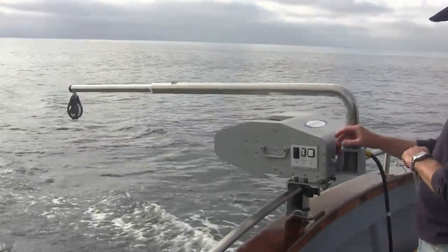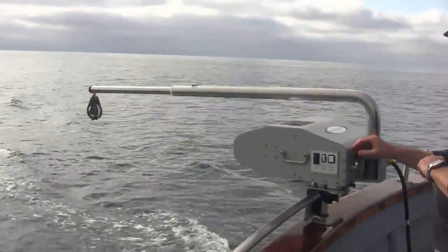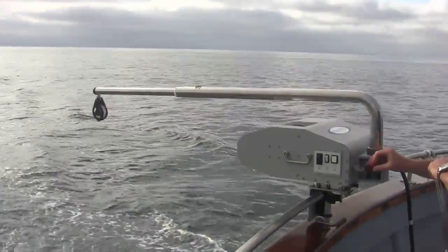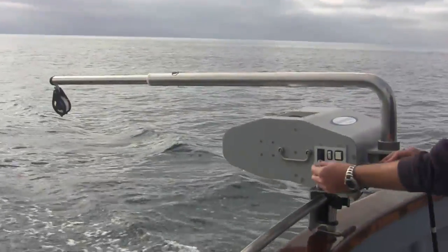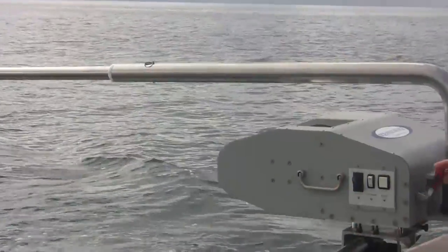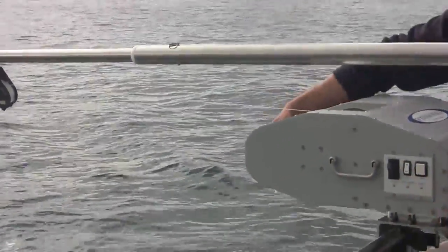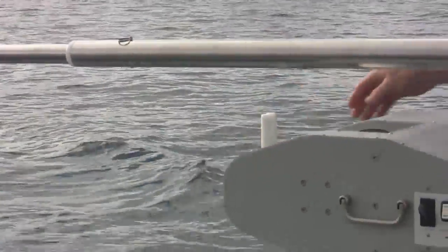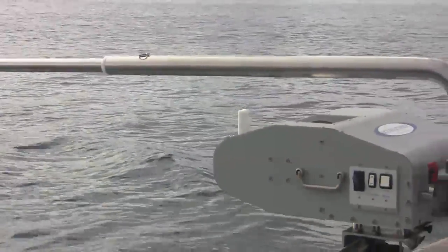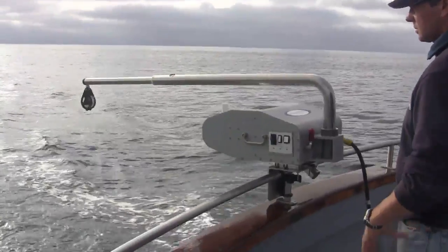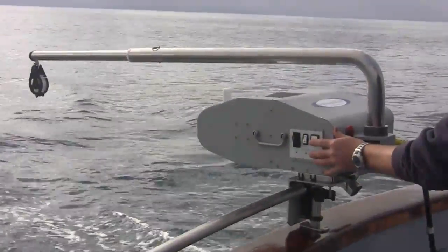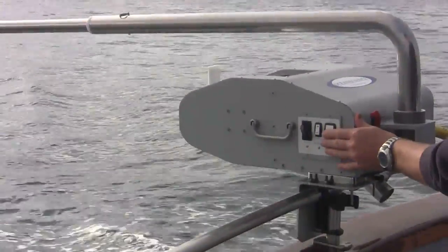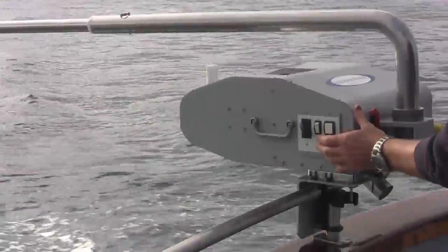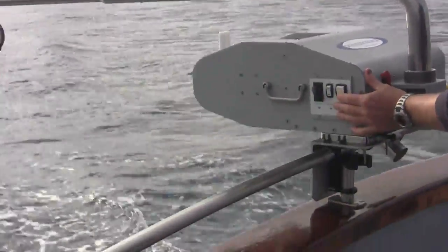So when the designated time has elapsed, the brake is applied, and then the clutch moves to the full position to lock the spool. Then you can let go of the brake, turn the level wind on, and then you can turn the winch motor onto fast to recover the probe. When the probe's close to the ship, again move on to the slow setting to recover the probe carefully close by.